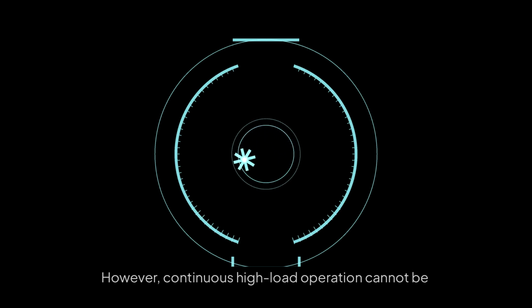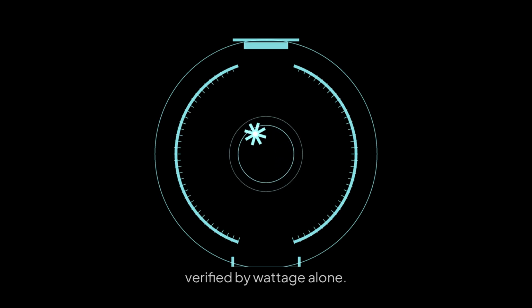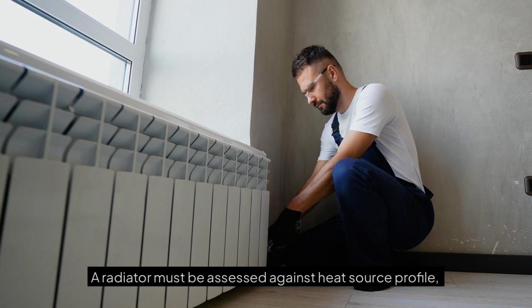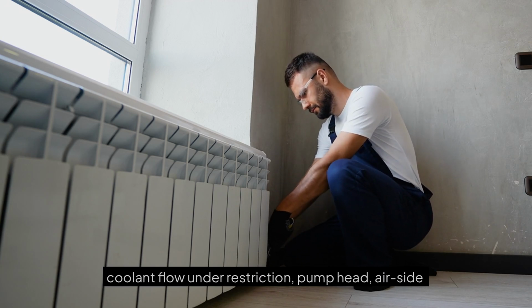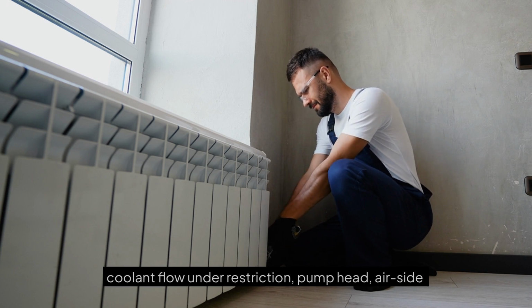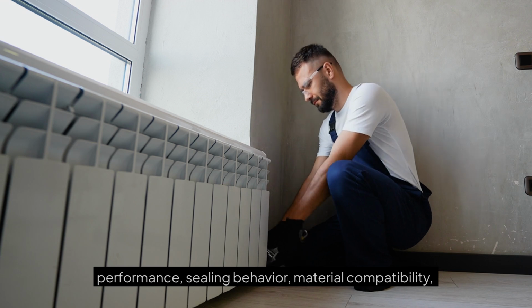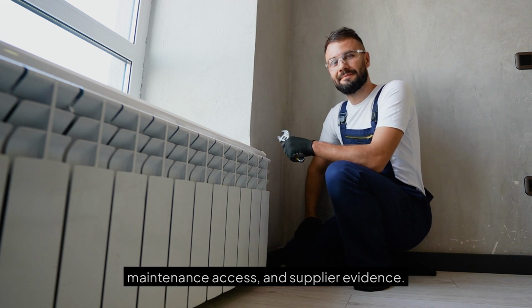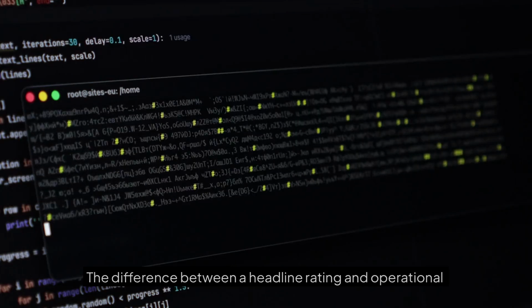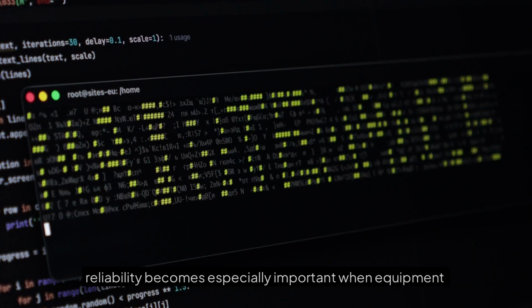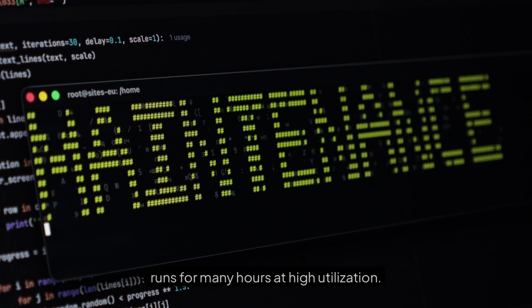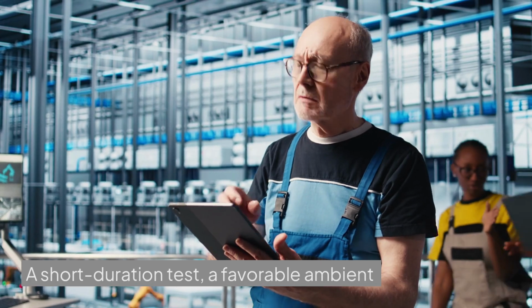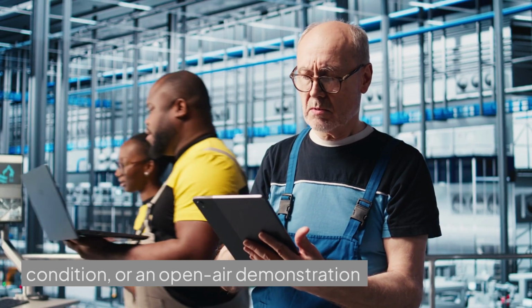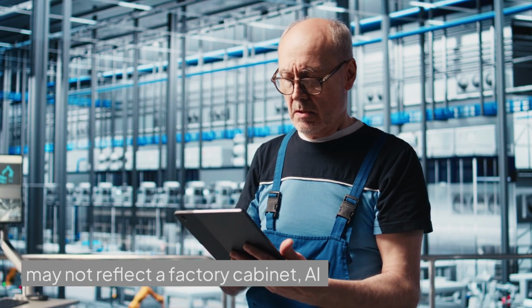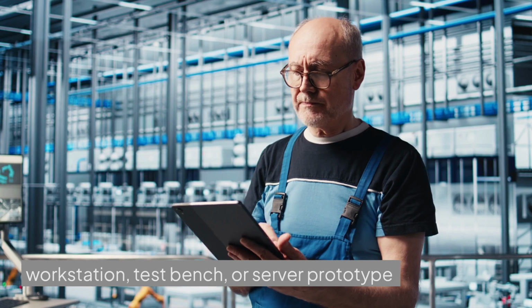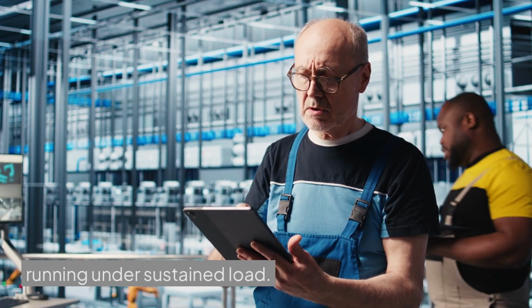However, continuous high-load operation cannot be verified by wattage alone. A radiator must be assessed against heat source profile, coolant flow under restriction, pump head, airside performance, sealing behavior, material compatibility, maintenance access, and supplier evidence. The difference between a headline rating and operational reliability becomes especially important when equipment runs for many hours at high utilization. A short duration test, a favorable ambient condition, or an open-air demonstration may not reflect a factory cabinet, AI workstation, test bench, or server prototype running under sustained load.